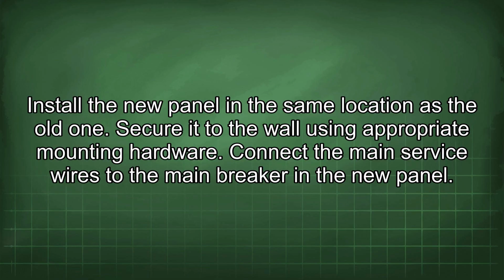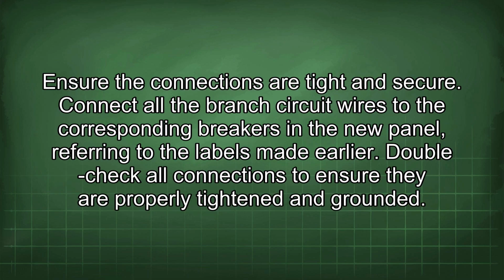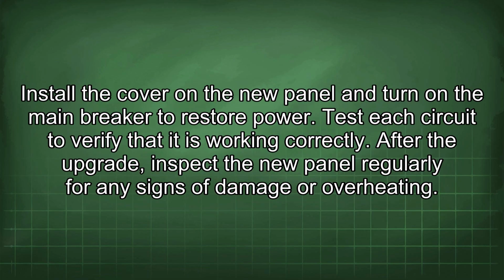Connect the main service wires to the main breaker in the new panel. Ensure the connections are tight and secure. Connect all the branch circuit wires to the corresponding breakers in the new panel, referring to the labels made earlier. Double-check all connections to ensure they are properly tightened and grounded. Install the cover on the new panel and turn on the main breaker to restore power. Test each circuit to verify that it is working correctly.